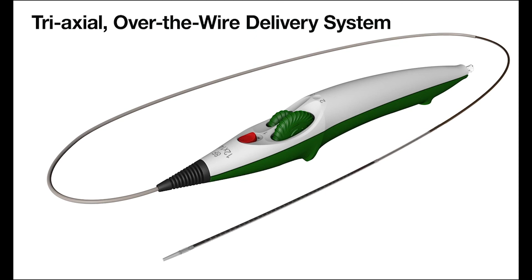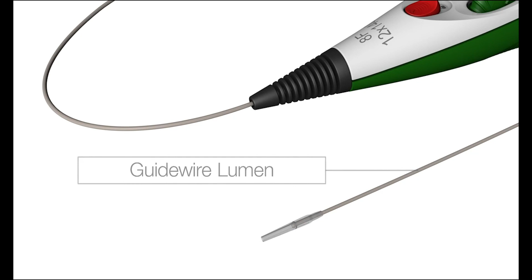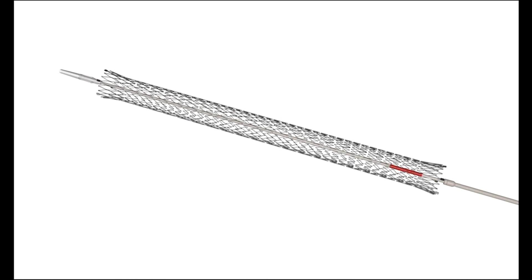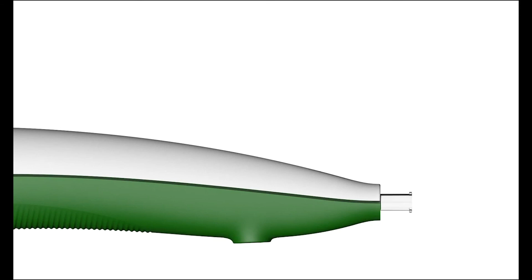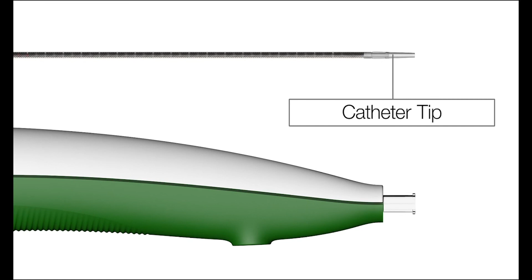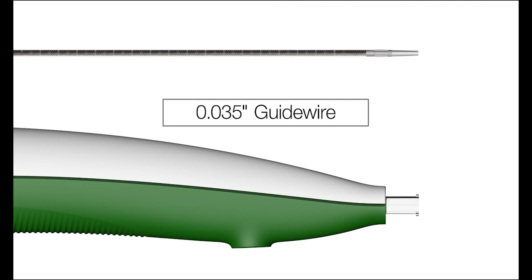The Venovo venous stent is loaded on a triaxial over-the-wire delivery system. The catheter is comprised of a guide wire lumen, stent delivery sheath, and system stability sheath. The stent is constrained in the space between the guide wire lumen and the stent delivery sheath. The guide wire lumen originates proximally on the handle with a Luer hub and terminates distally at the catheter tip. The guide wire lumen is designed to accept a compatible 035 guide wire.